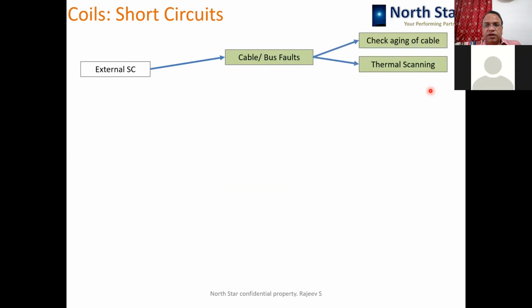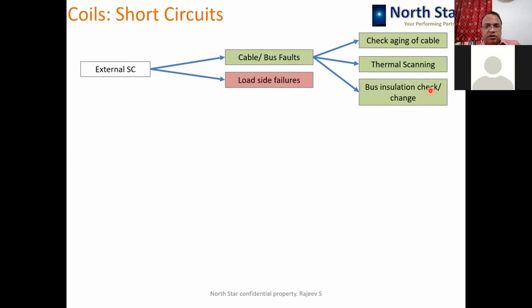Now coming to winding and coils, short circuit happens in the transformer winding because of external short circuits. That can be because of a fault in the cable or bus duct. So you can do thermal scanning, and aging of the cable can be checked. Bus insulation can be monitored and checked from time to time. Load side failures happen because of different reasons. Fault current can be limited by putting series reactors in the circuit.